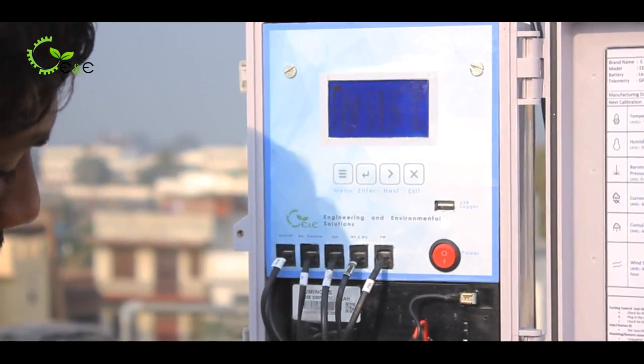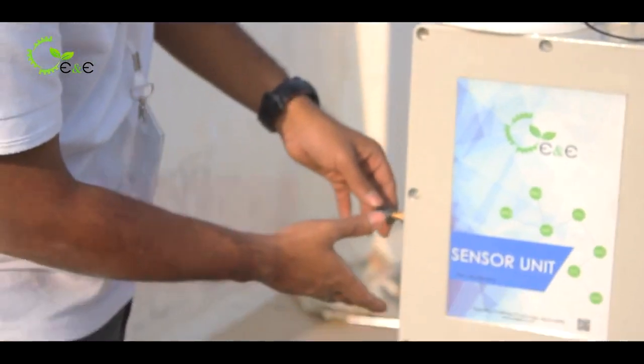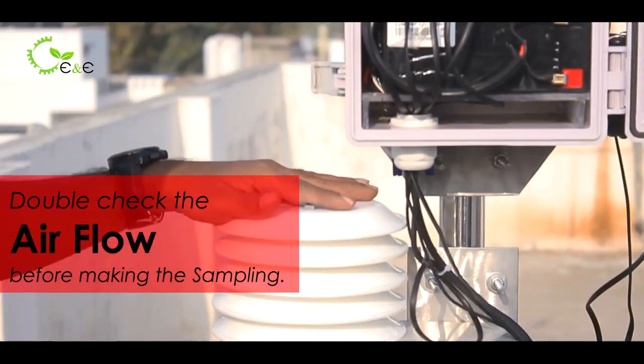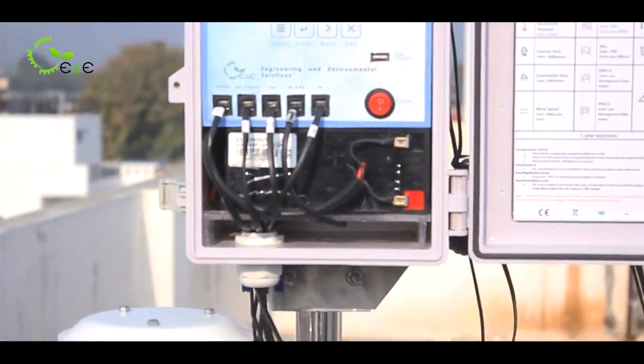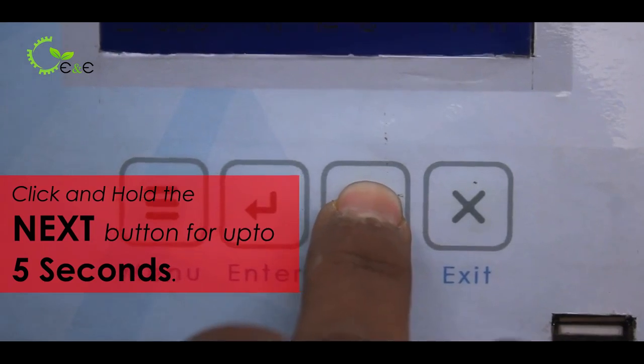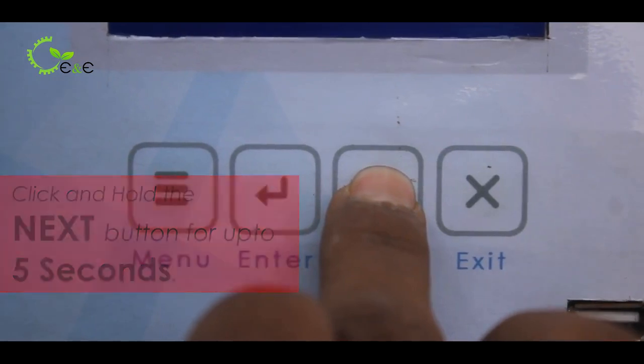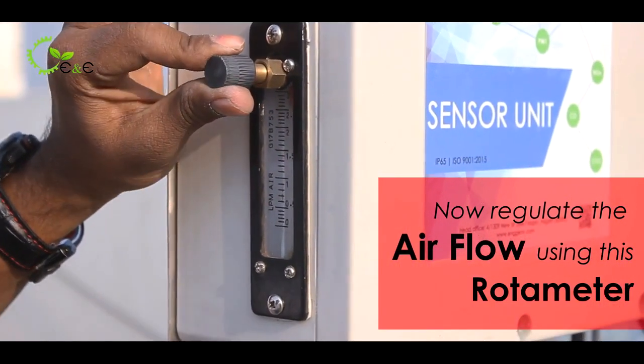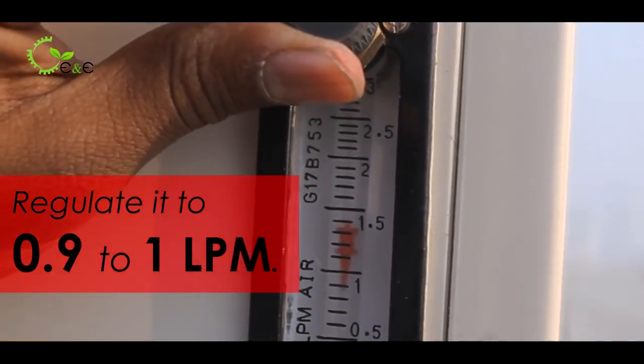Now comes our sensor unit. We are using a pump and a rotameter to regulate the airflow. You have to double check before making the sampling, as sampling happens every one hour interval. To regulate the flow, press the next button for 5 plus seconds — the pump will start. Now you can regulate the airflow using the rotameter. Make sure you always regulate it to 0.9 to 1 LPM.